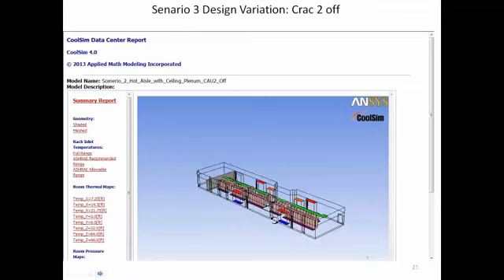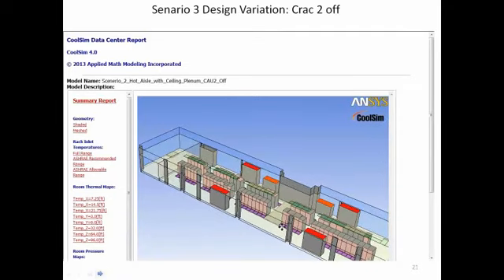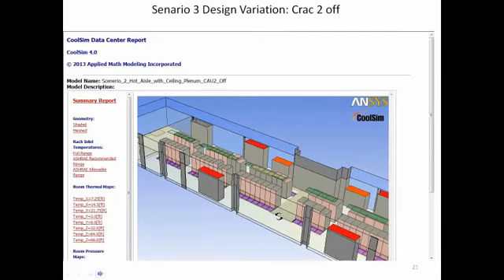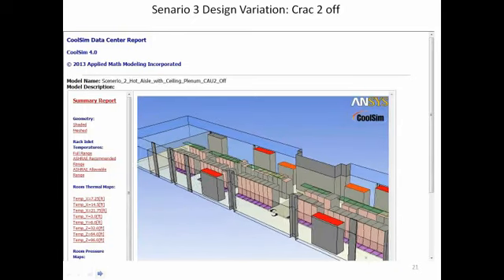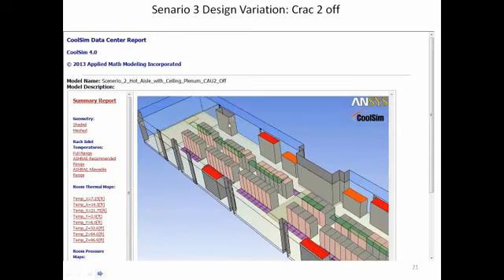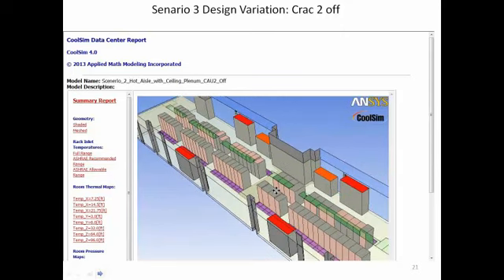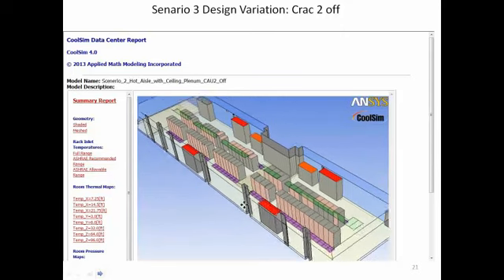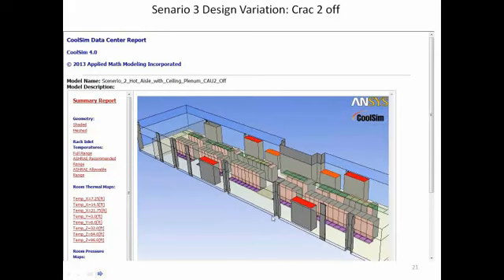Let's chase it a little further. Now here what you've done is turn a CRAC unit off. This is a test to see, in fact, if it can run N+1. So here you've chosen this one in the upper left-hand corner and switched that off. And this is going to affect a couple of different things. For one, it's going to give us a better RTI because we've just dropped approximately 10,000 CFM of air out, and we didn't need it anyway.